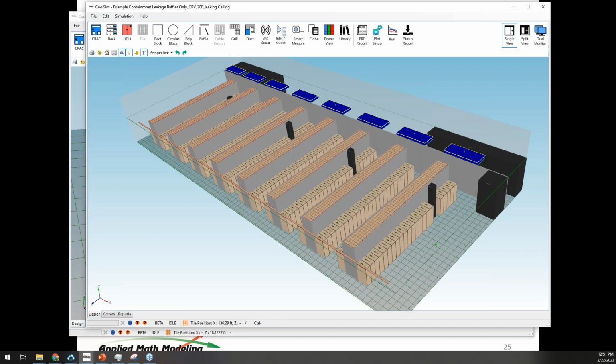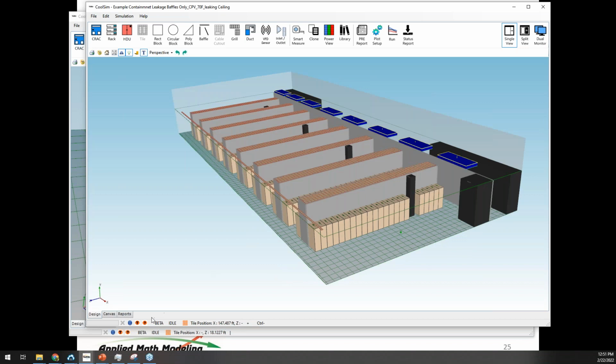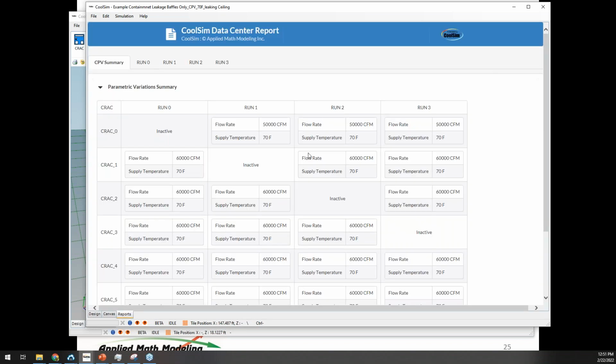Again, what we're doing in CFD modeling is we're making assumptions. We have to, because there's no real data on much of this. There's no real data on how leaky a rack is. There's not even real data on servers. We don't know a lot about the servers. My job early in my life was to build thermal control systems for servers. They're all a little different. They behave a little differently, and the manufacturers aren't particularly excited about sharing that information with us.